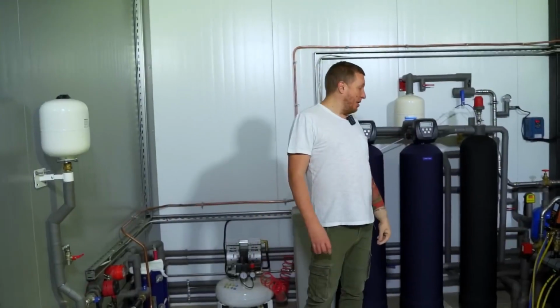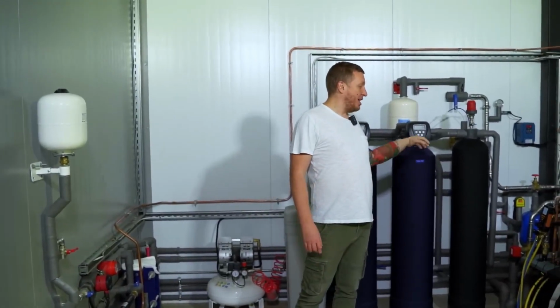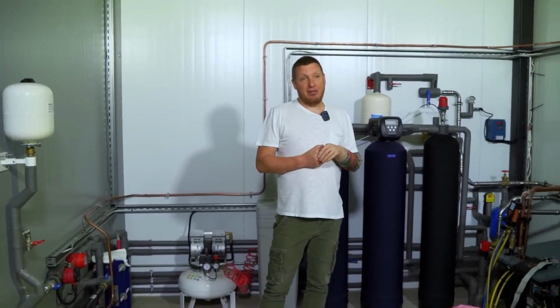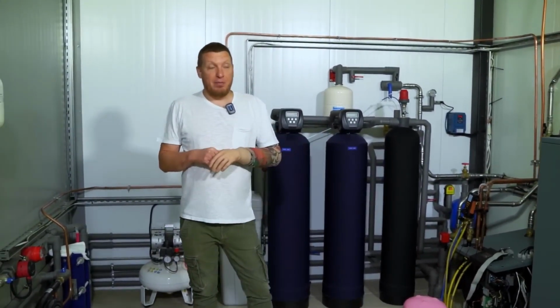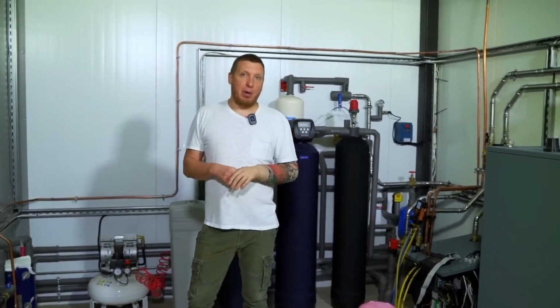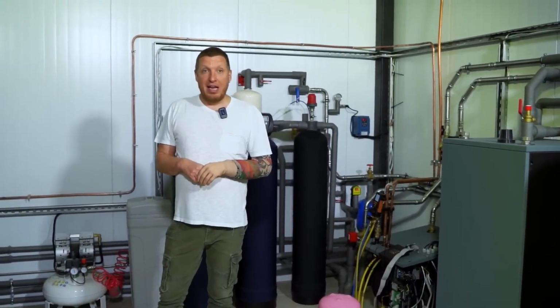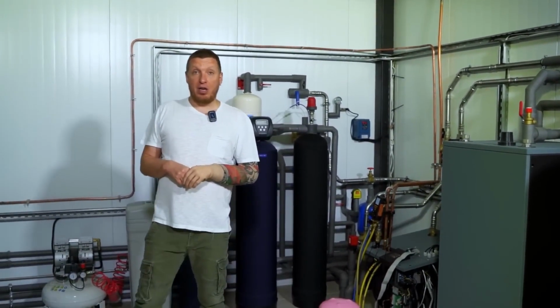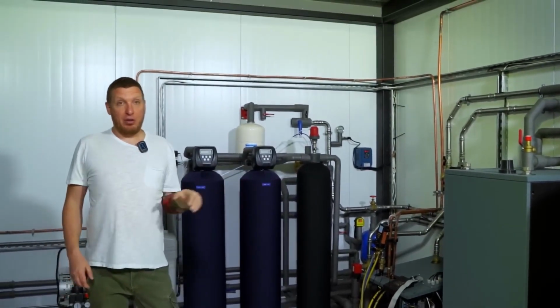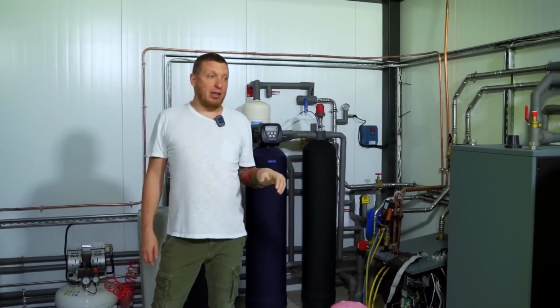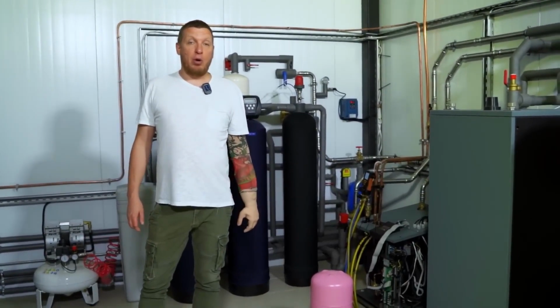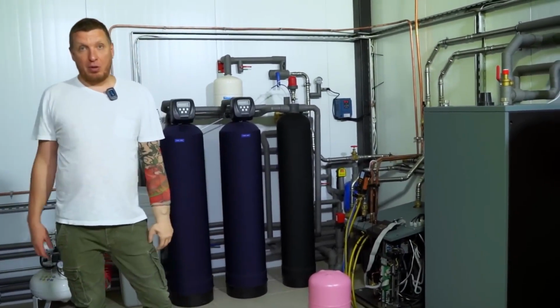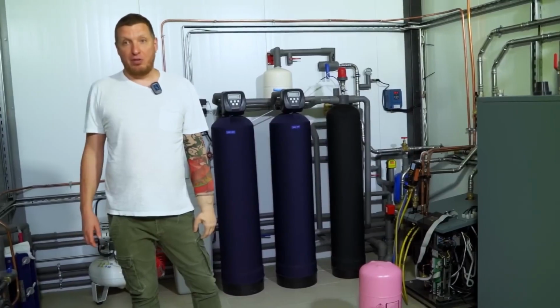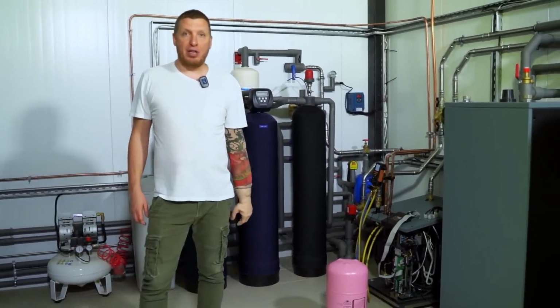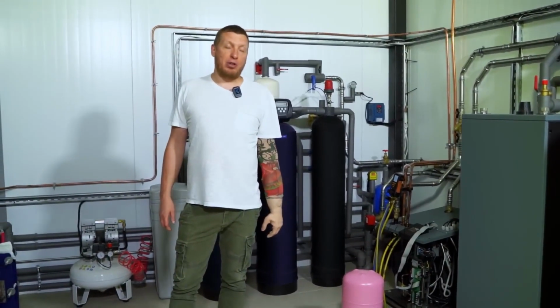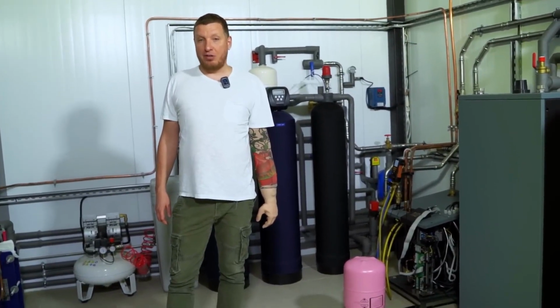For this heat pump, the source of low potential energy is water from a well, which is always at 7 to 8 degrees Celsius. As it passes through the heat pump, it cools down to 4 degrees and is then discharged either into a pond, there's a pond not far from here, or we're testing how it will work if we discharge it into an overflow well located at the other end of the property. Will it silt up or not? We'll find out. I think everything will be fine. The well here is in limestone and its absorbency is quite good.